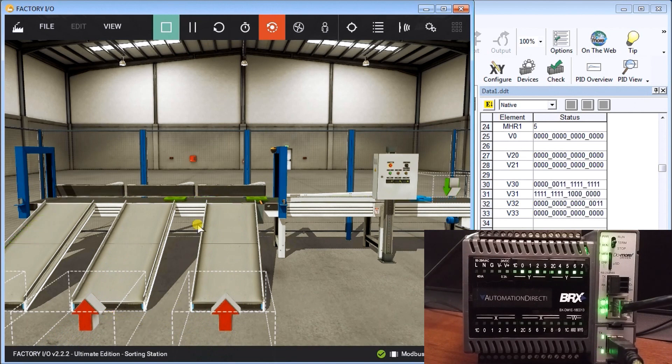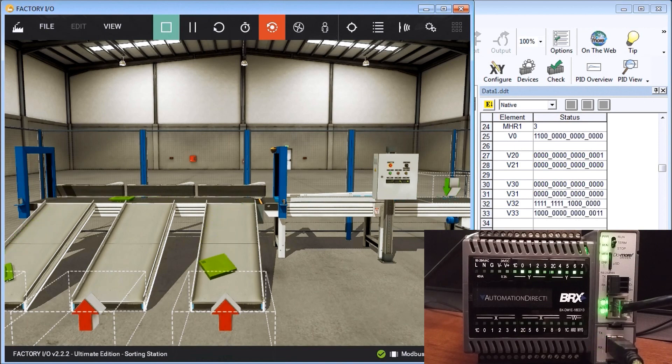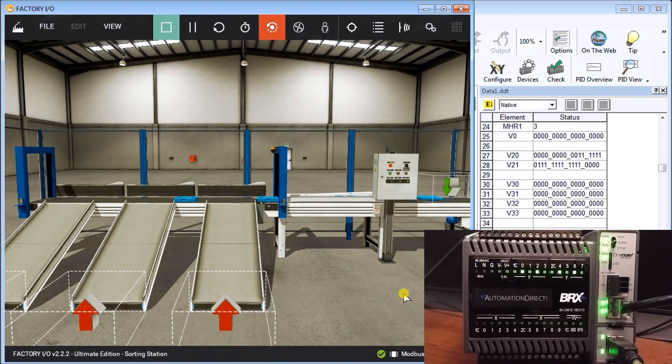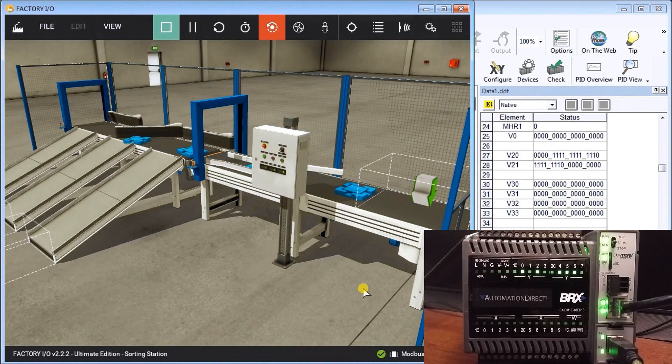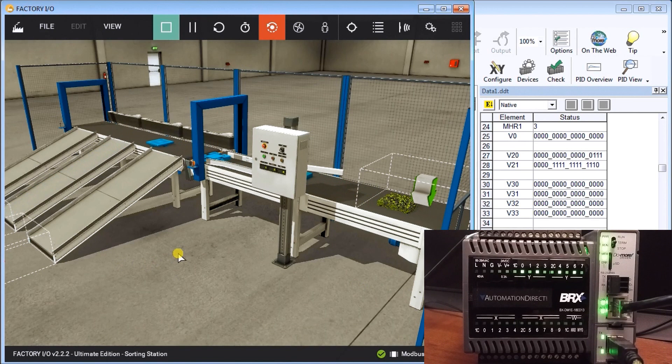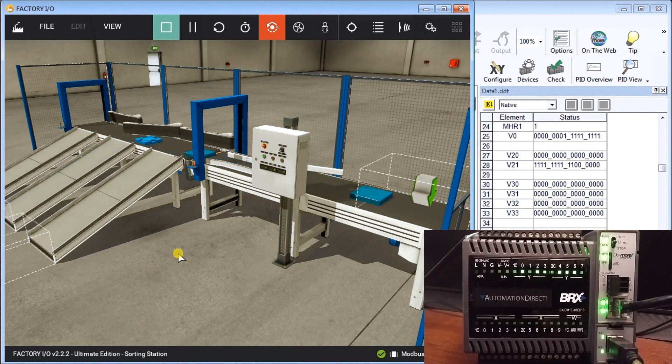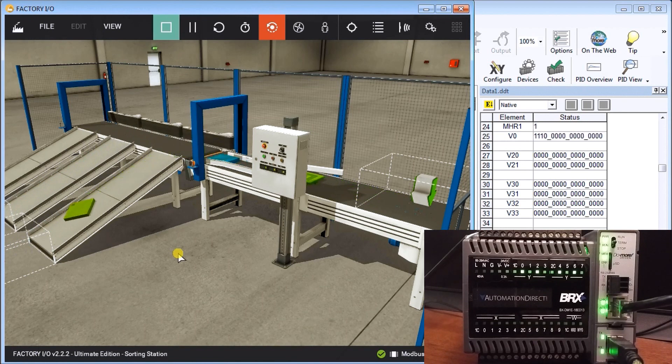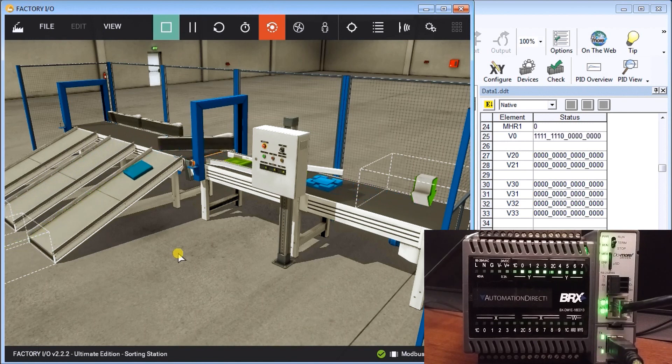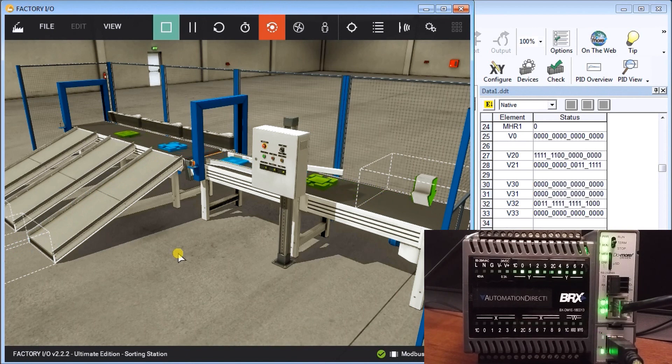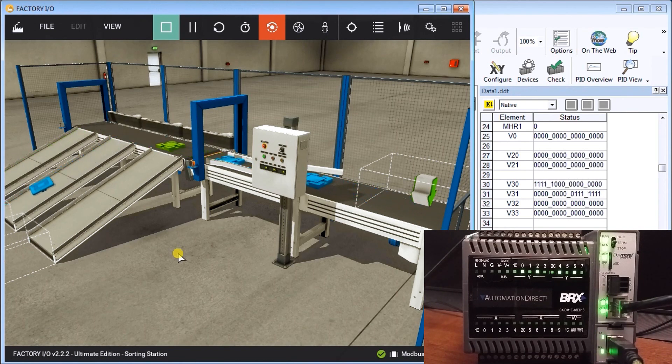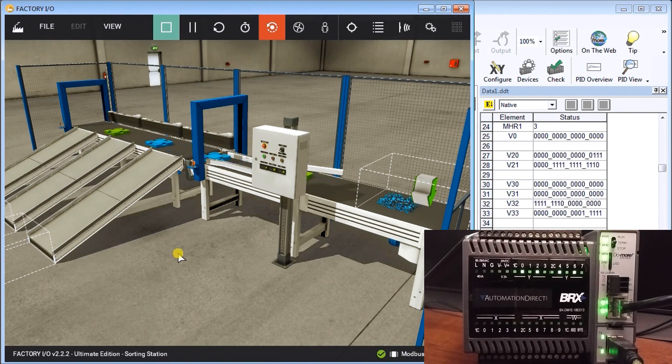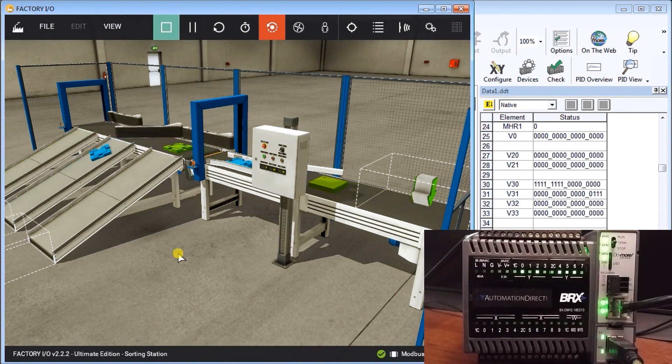On my left side, we can see the bits shifting in our shift register to tell which direction we're putting them in. As they come down the conveyor belt, we energize that output to fire off to direct that product. Testing the program is vital to the development of the program itself. We've used shift registers to track along that conveyor system and reject or sort those products out according to what is seeing on that sensor.